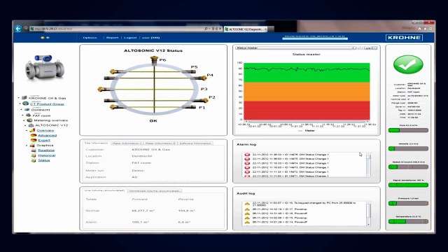You see here different numbers. As long as these numbers are below 33, the meter is okay. There is no reason to worry. Between 33 and 66, we give a warning. There could be light contamination in a meter, for example. The meter is still within custody transfer, but some long-term attention is required. If values are higher than 66, we give a real alarm. This means strong contamination, more than 2 paths failed, the meter is outside of custody transfer accuracy, and immediate action is required.